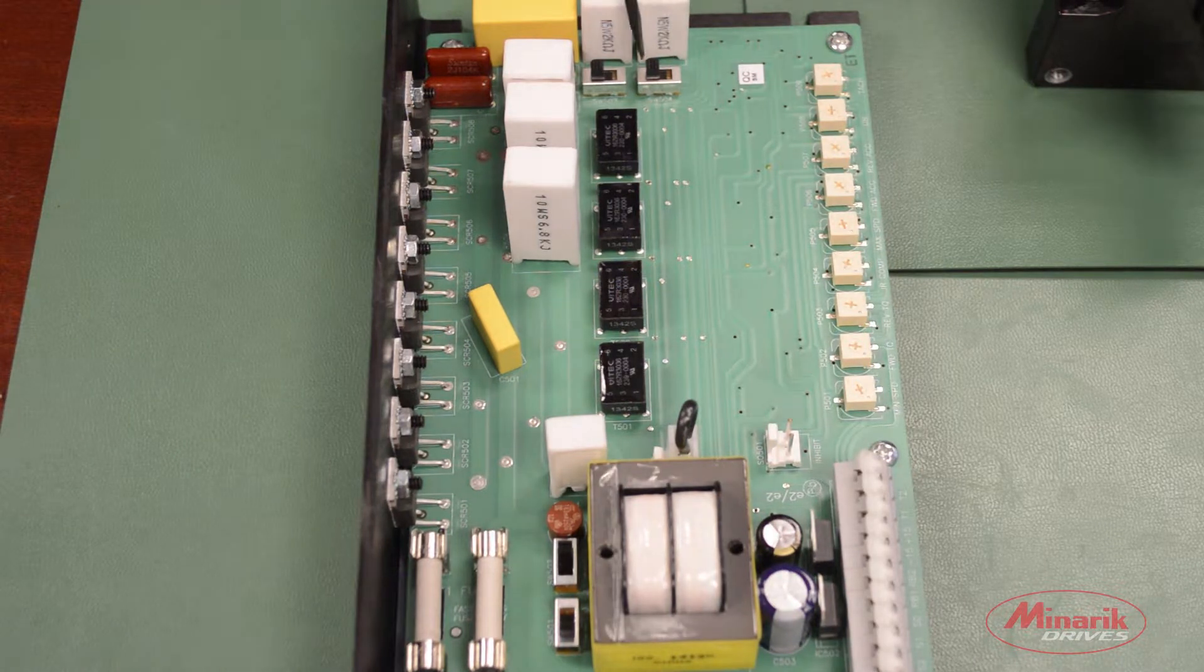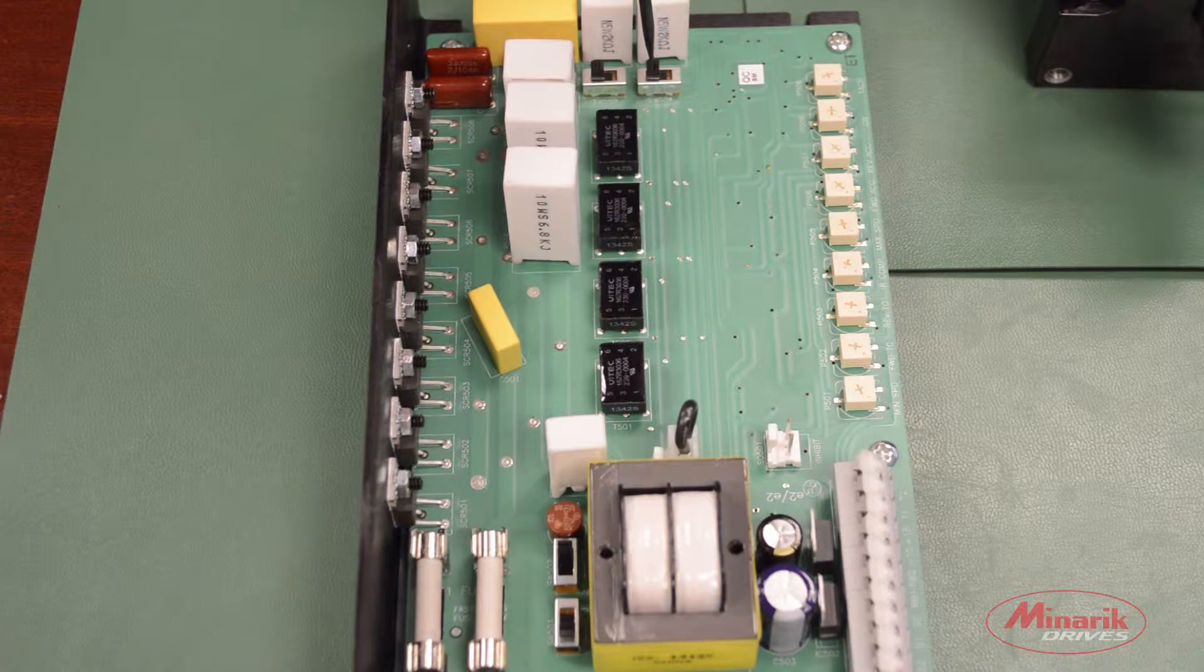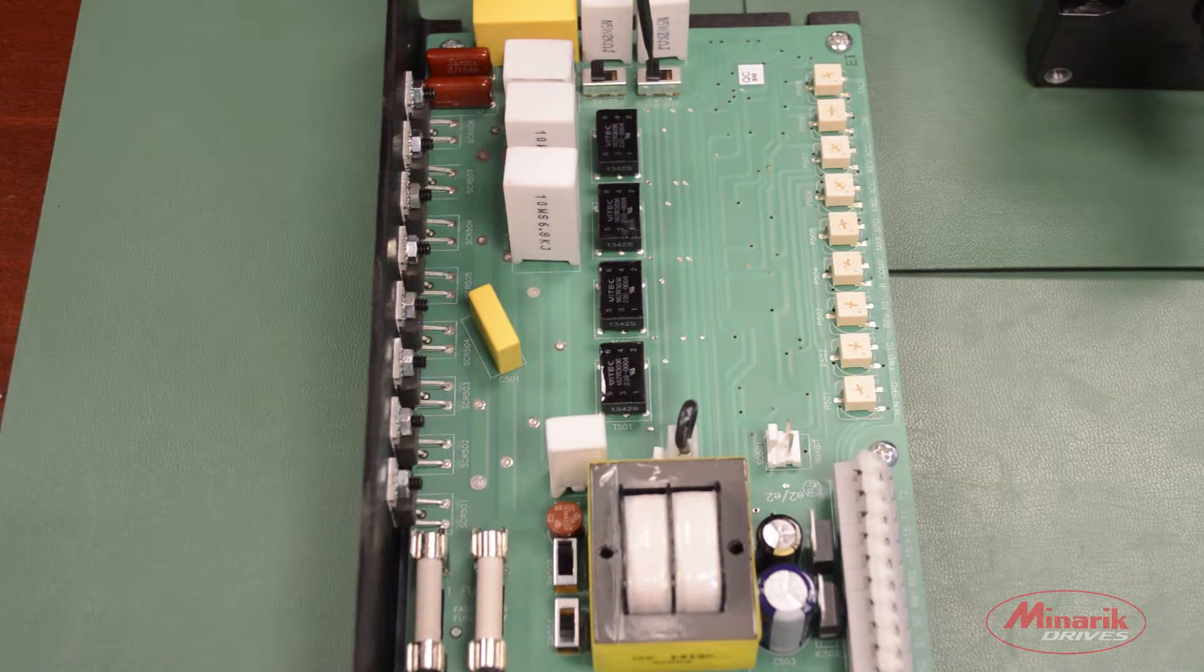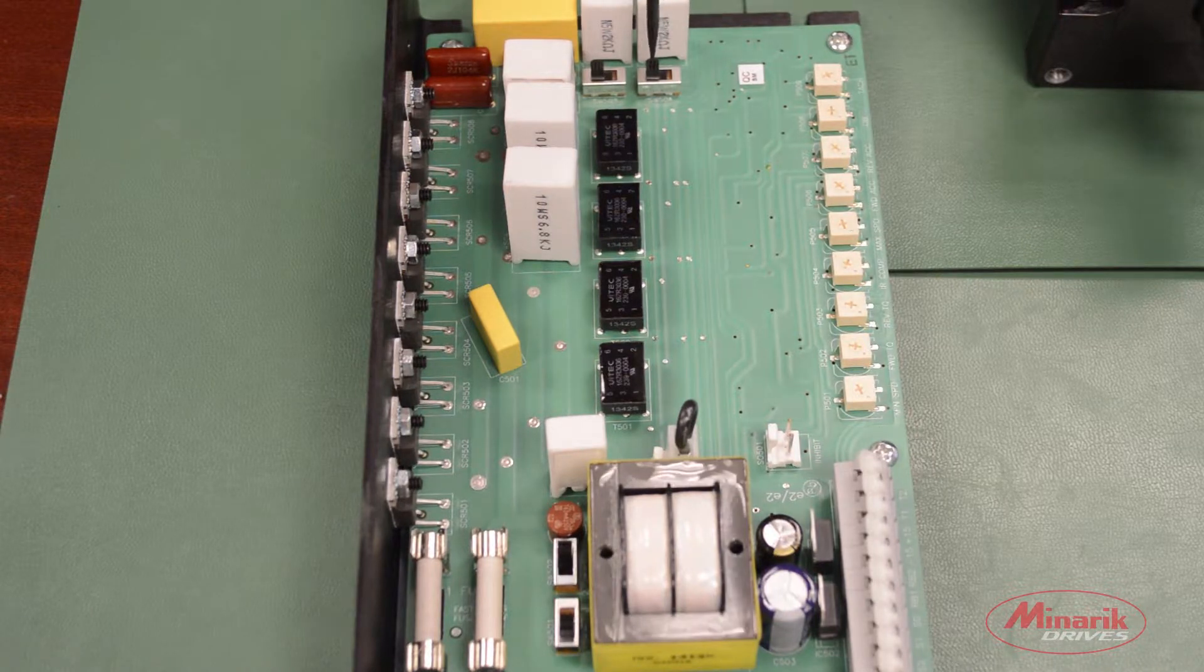The last switch to look at is the feedback switch. This sets whether you're using tach feedback or armature feedback. We're not going to be using tach feedback so we'll make sure that the switch is located in the armature feedback position which is the factory default position.